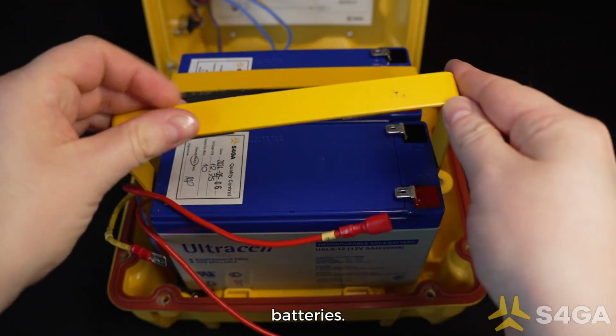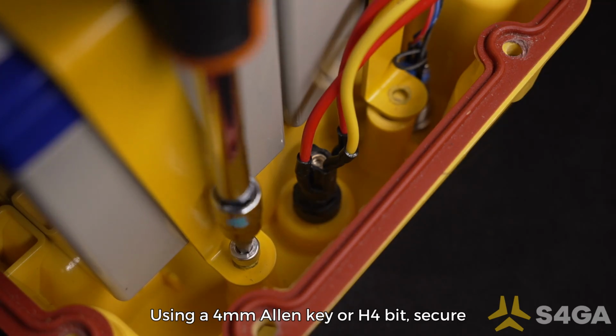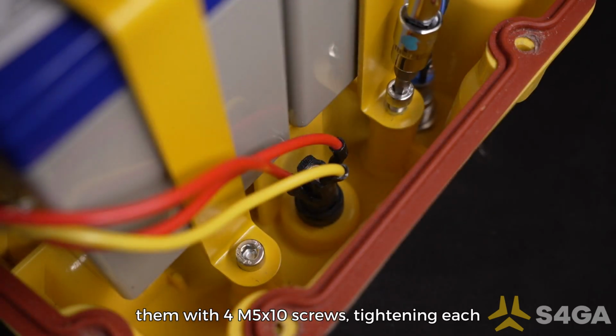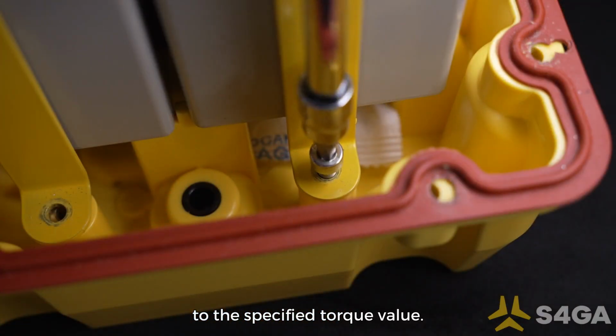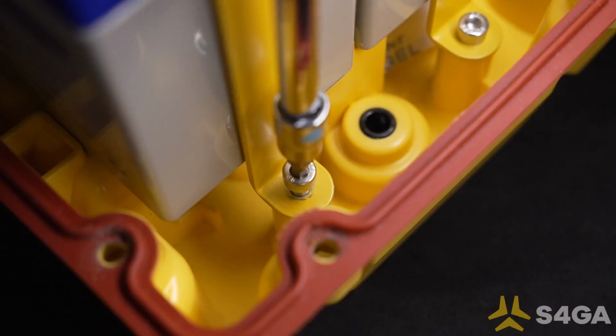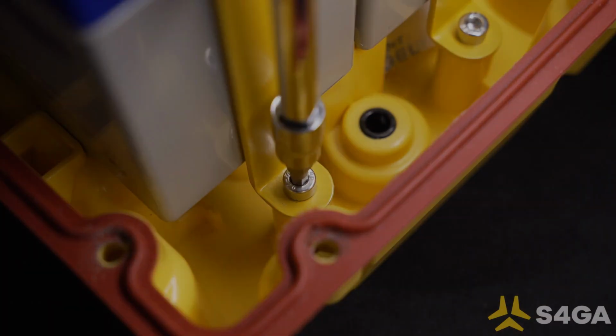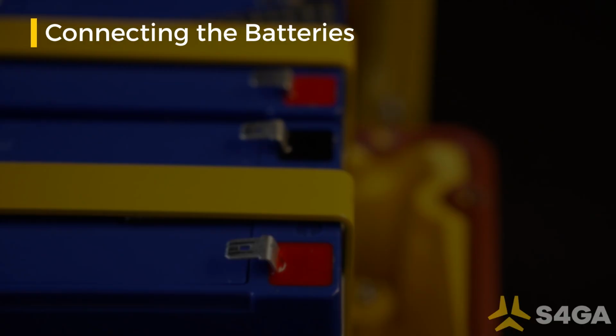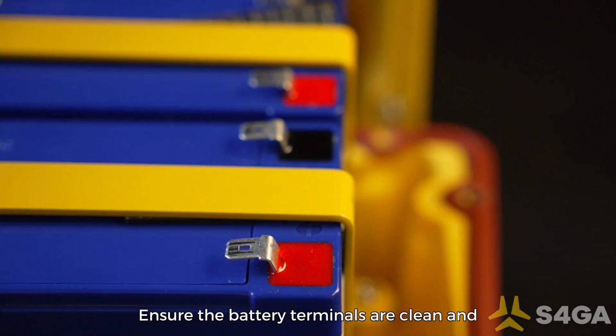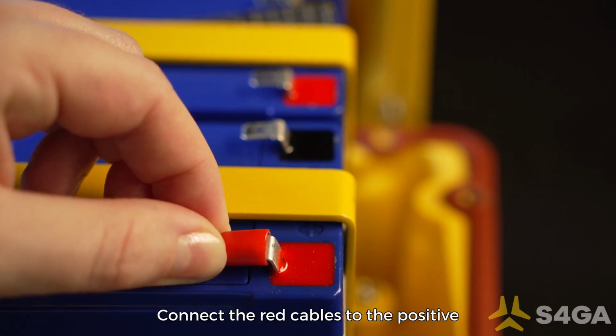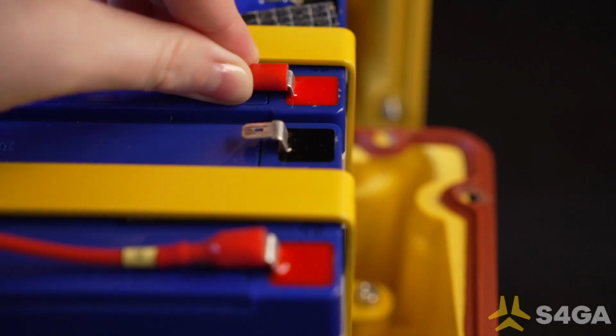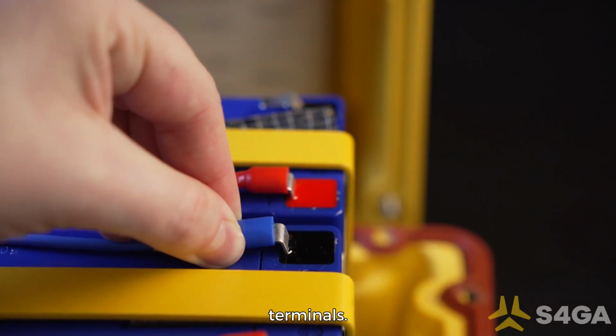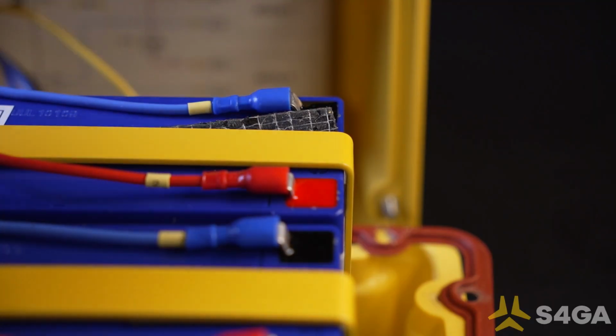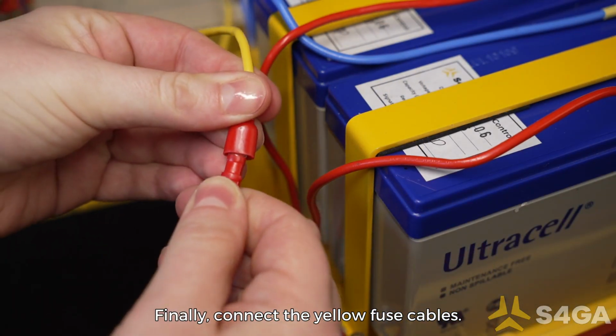Position the battery holders over the batteries. Using a 4mm Allen key or H4 bit, secure them with 4 M5x10 screws, tightening each to the specified torque value. Ensure the battery terminals are clean and free from corrosion. Reconnect the cables in the following order. Connect the red cables to the positive terminals. Connect the blue cables to the negative terminals. Finally, connect the yellow fuse cables.